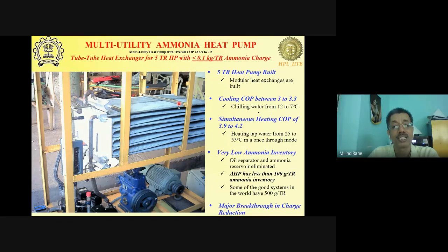Now the newer designs, with appropriately modified tubes and heat exchanger manufacturing technique, will be in a position to bring it down even below this. If you look at this, it is producing cooling with a COP of 3 to 3.3 while chilling water from 12 to 7, and concurrently it is delivering hot water with a COP of 3.9 to 4.2. So the overall COP of the system jumps up to 6.9 to 7.5, which is extremely good. Higher COP means lower energy input. Lower energy input means lower environmental impact. And if a single system can produce two utilities, you will be using less refrigerant. So again, the environmental effects will be much better.